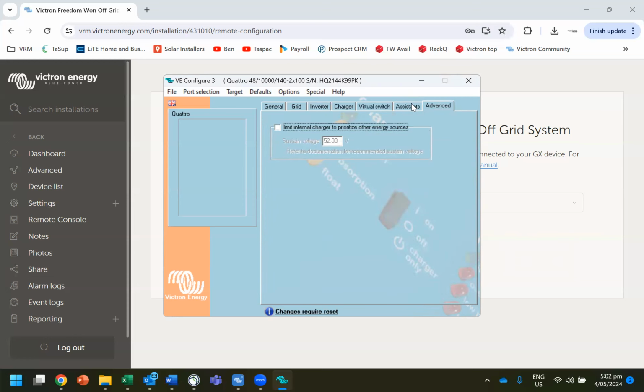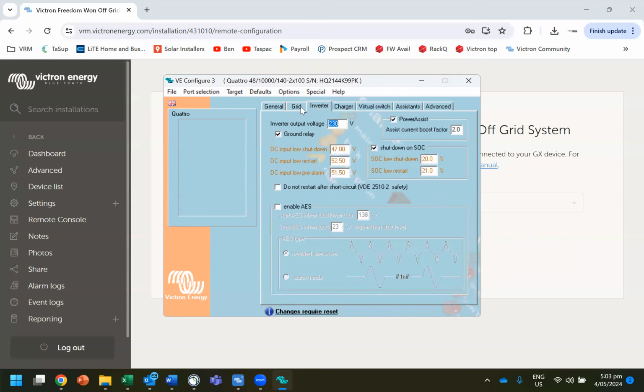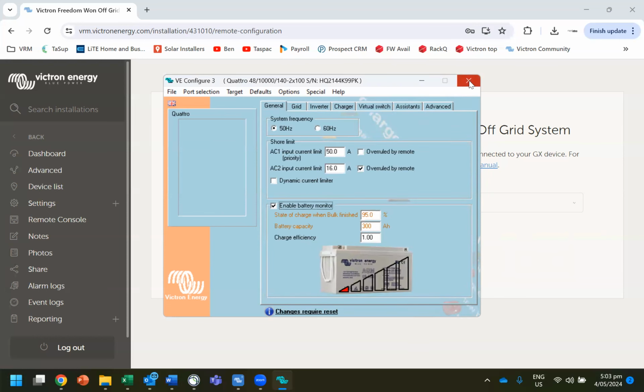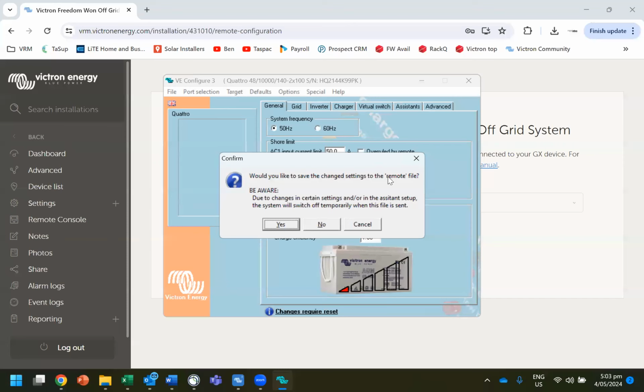Advanced, we don't need to worry about that. So that is pretty much the programming done for the inverter. So then you just close this down. It's going to ask if you want to save it, and you go yes. And it says a little warning there, be aware, due to changes in certain settings, it will switch off temporarily when the file is sent. So be aware that you're going to lose power to the site. Now, this is important to know because you've got an internet connection here on the site, and it's probably powered by the inverter. So it could take, I don't know, maybe 5 minutes before this system comes back online.